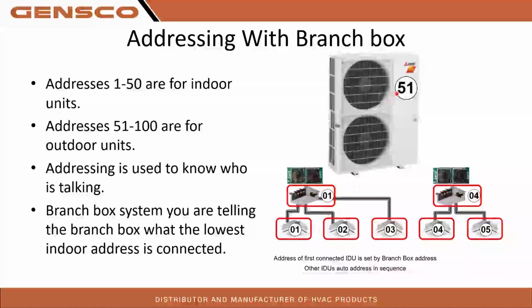And then for your heat pump, I would say probably 99% of your systems, you're going to end up addressing your heat pump as 51, because it is your lowest indoor address. So in this case, address 1 right here, plus 50 equals your outdoor address. So that's what you end up seeing right there. That's how we got that 51.